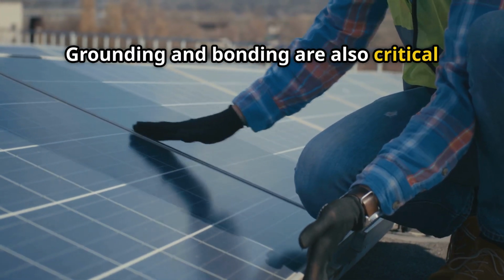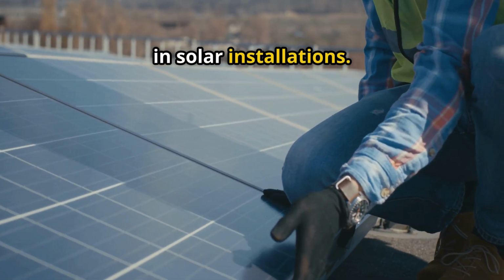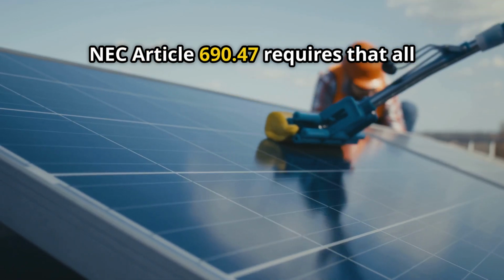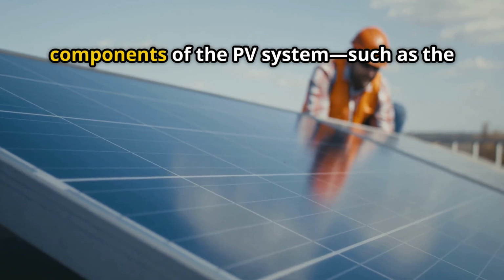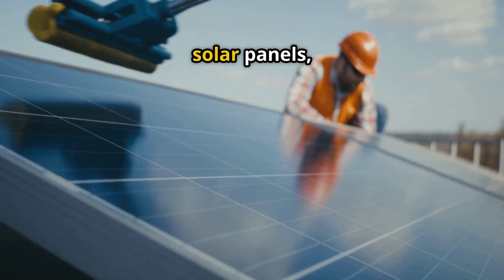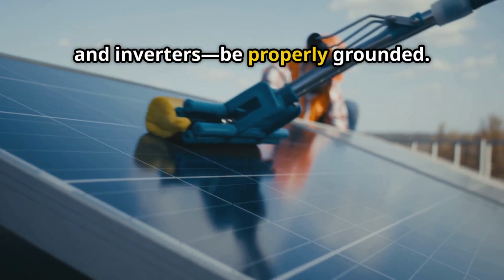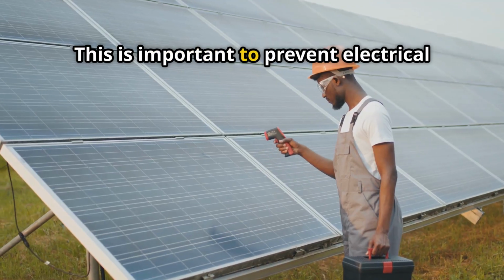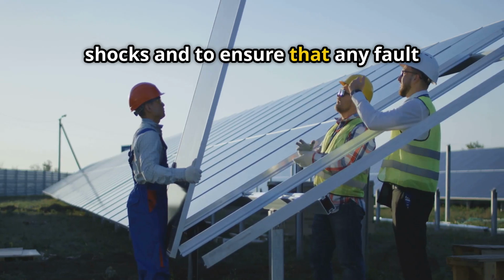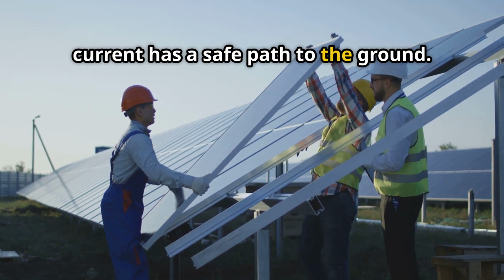Grounding and bonding are also critical in solar installations. NEC Article 690.47 requires that all components of the PV system, such as the solar panels, racking, and inverters, be properly grounded. This is important to prevent electrical shocks and to ensure that any fault current has a safe path to the ground.